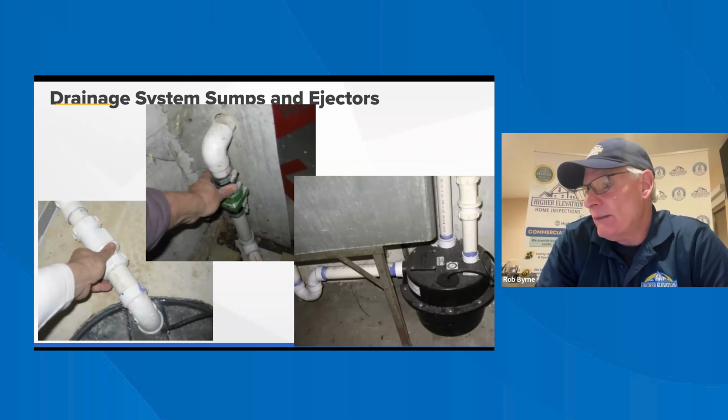These are examples of some pumps that are just taking care of groundwater or water coming in. These are not such a good application because it's just sitting in the dirt and it clogs everything. Usually, like you saw in the other pictures, you'll have on the bottom a container or plastic piece in the ground, and it'll just let the water come in and keep the dirt and debris out. This is primitive.